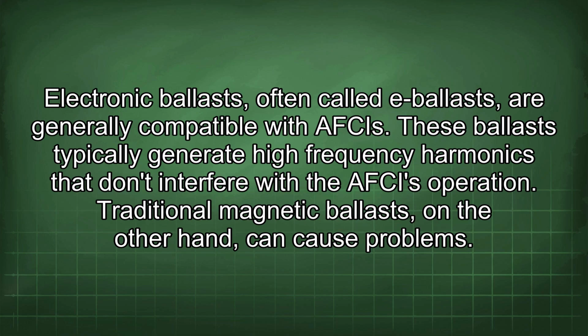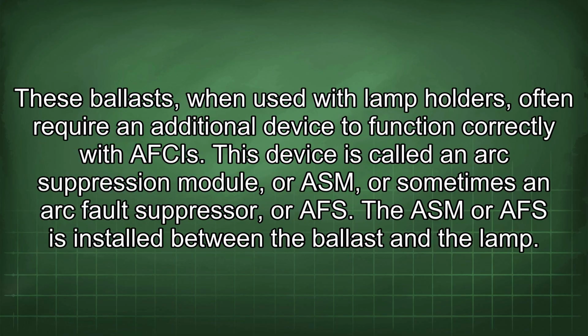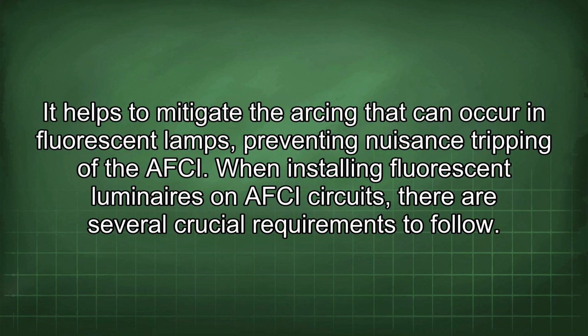Traditional magnetic ballasts, on the other hand, can cause problems. These ballasts, when used with lamp holders, often require an additional device to function correctly with AFCIs. This device is called an arc suppression module, or ASM, or sometimes an arc fault suppressor, or AFS. The ASM or AFS is installed between the ballast and the lamp. It helps to mitigate the arcing that can occur in fluorescent lamps, preventing nuisance tripping of the AFCI.